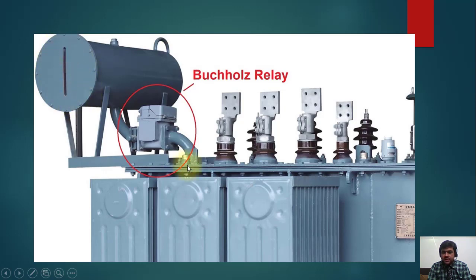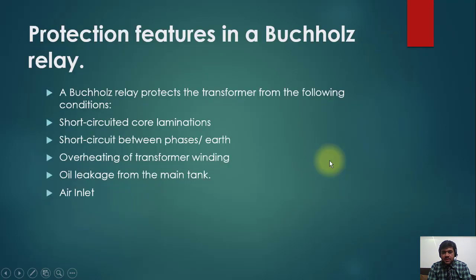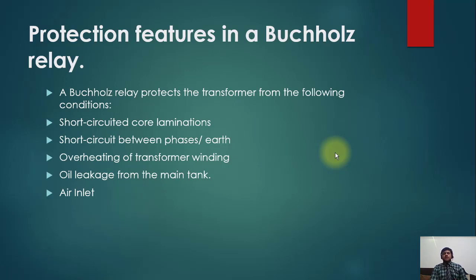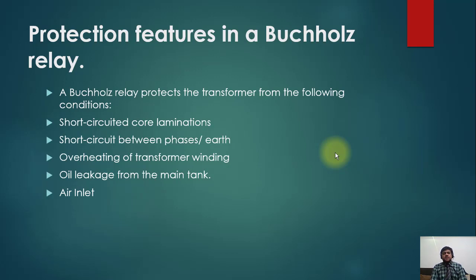What are the protection features of a Buchholz relay? A Buchholz relay protects the transformer from the following conditions: short circuit of core laminations, short circuit between phases or earth, heating of transformer windings, oil leakage from the main tank, and air inlet.